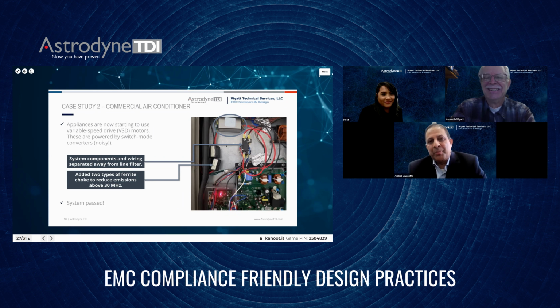We saw a similar, pretty interesting case with one of the companies that make products for the semiconductor manufacturing industry. They have a control box where all the electronics and controls come in. They supply these boxes to multiple OEMs, 500 units to one and 500 to another, and each OEM has slightly different needs, so they have to rearrange or reconfigure the control a little bit. But in the end it's the same componentry, so the filter still passes. On the last go-around, the filter failed, and they asked, have you changed the filter? No, we haven't changed the filter, it's a standard product from the catalog, can't change.